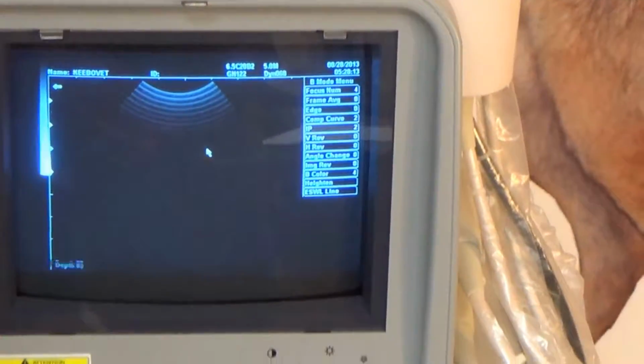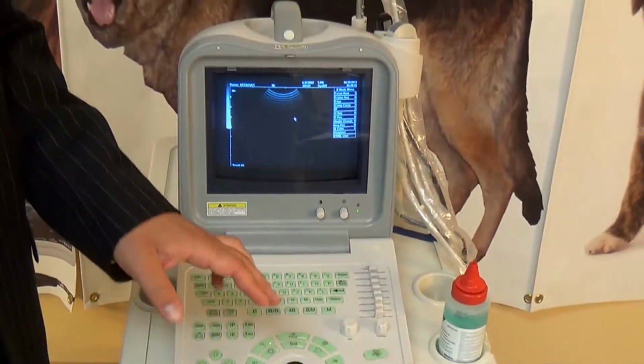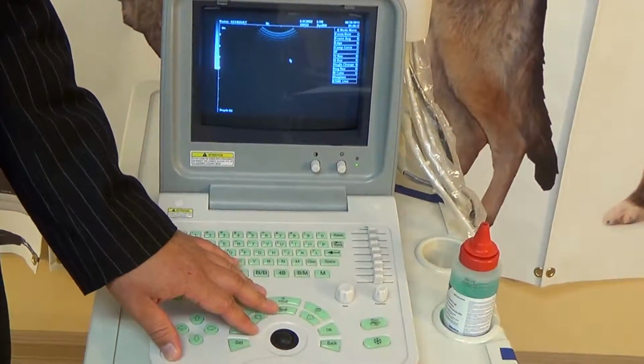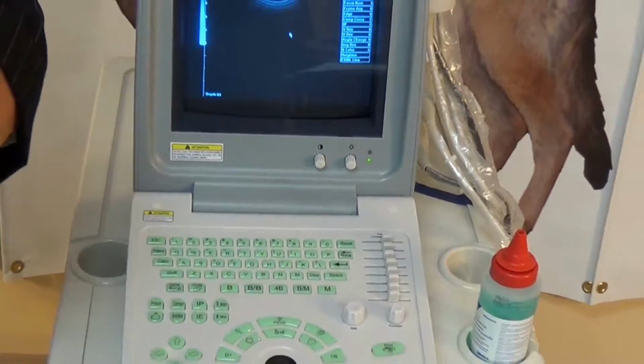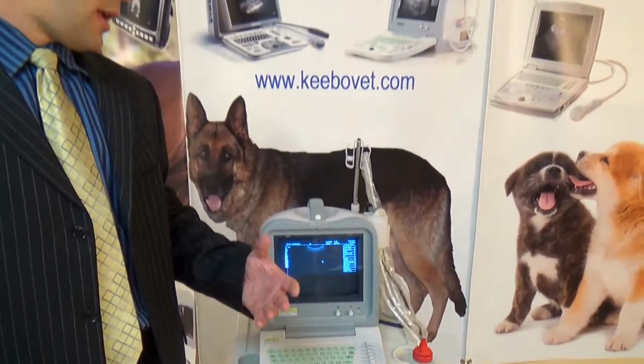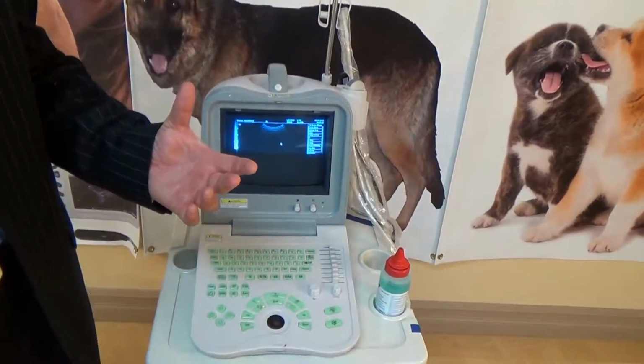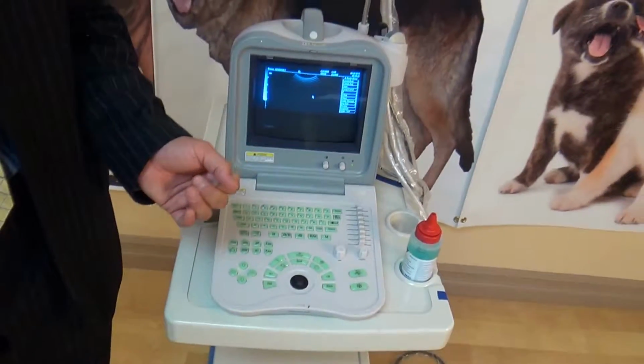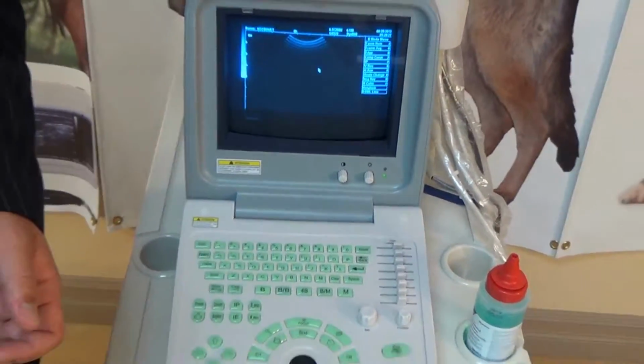If you want to go really deep or for a really large animal, you'll decrease the frequency to a lower setting so that you can go deeper and still get good resolution. But it will not be equivalent to the resolution that you'd have on something of 9 megahertz.